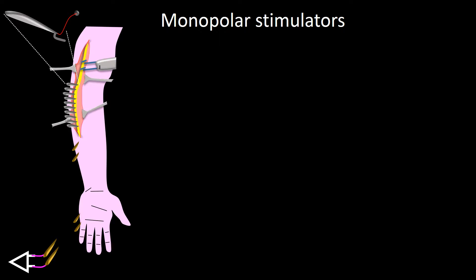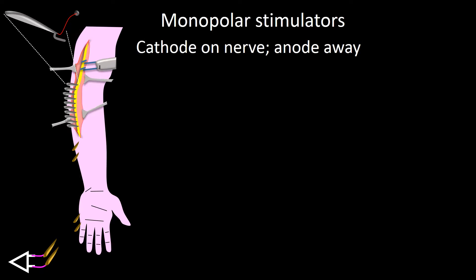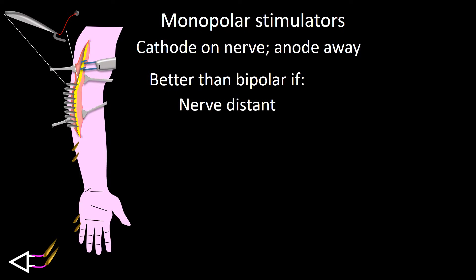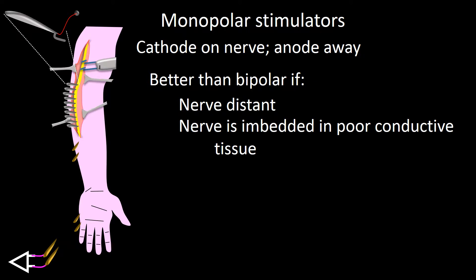Monopolar stimulators have the cathode placed on the nerve and the anode at a site not contaminated by nerve activity. They are better than bipolar if the nerve is distant, embedded in poorly conductive tissue, or if there is excessive fluid in the surgical field, since only one pole would be in the fluid — the other pole, the anode, being far from it — making short circuitry less likely.